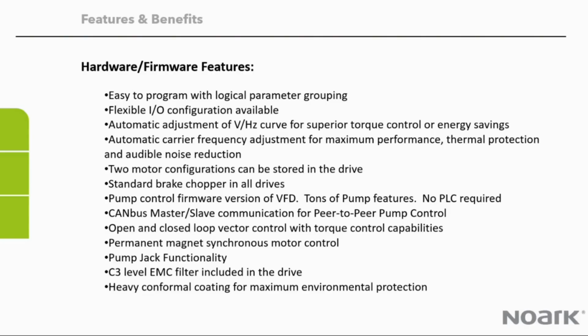It'll be quieter. Two motor configurations can be stored in the drive in case you have a process where you have to jump from one to the other. You can set that all up and then just by a digital input toggle between which one is being utilized. We talked about the brake chopper to take care of regenerative energy. Not all applications need that. We can also add pump control firmware or replace the firmware that's in the drive with pump control firmware. Adds a ton of pump features.